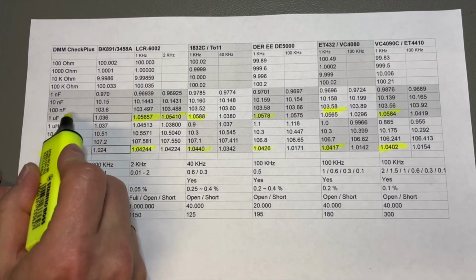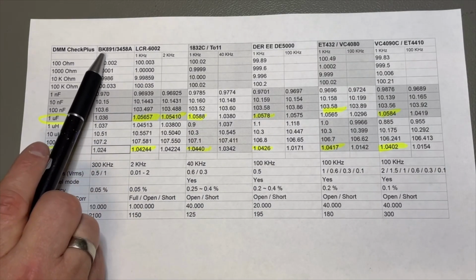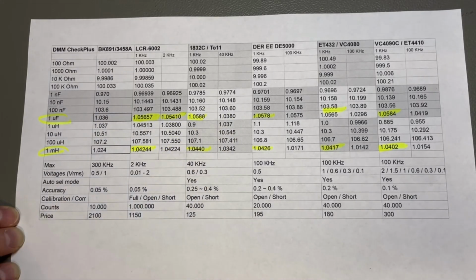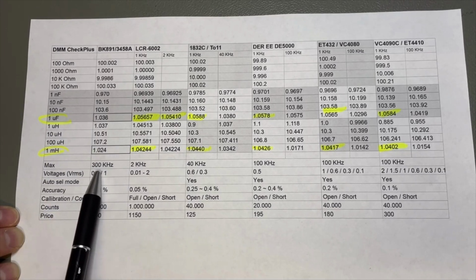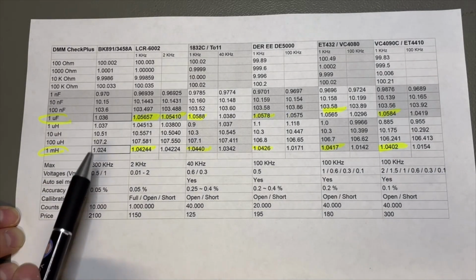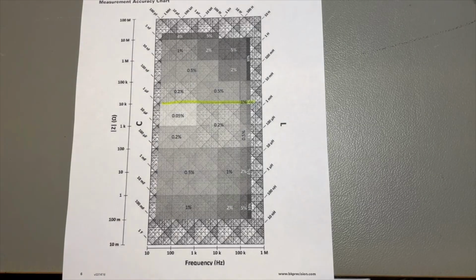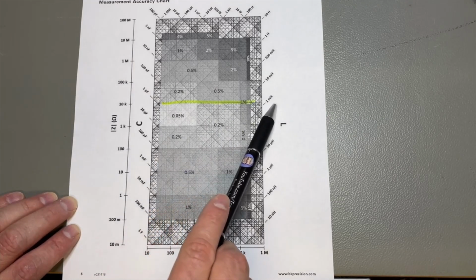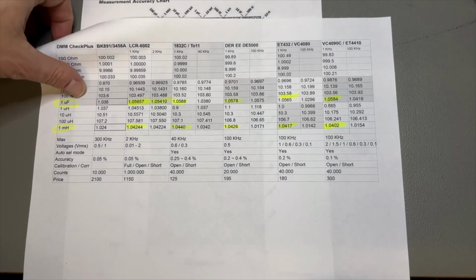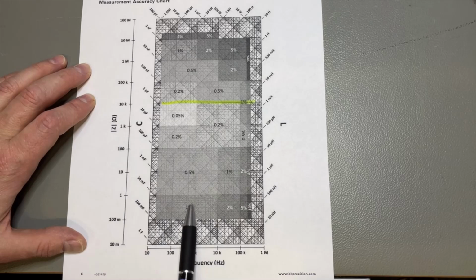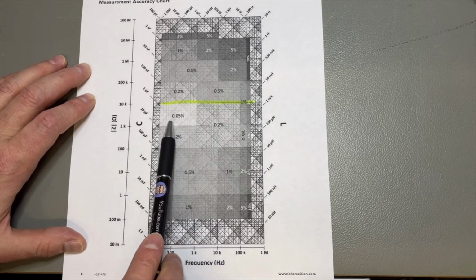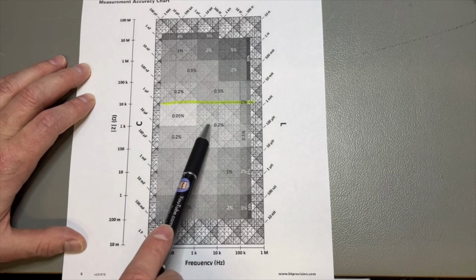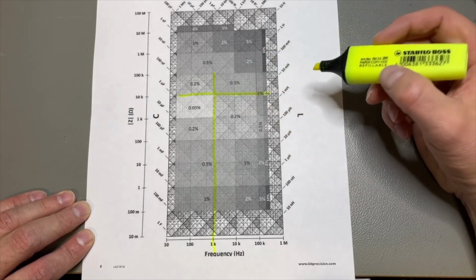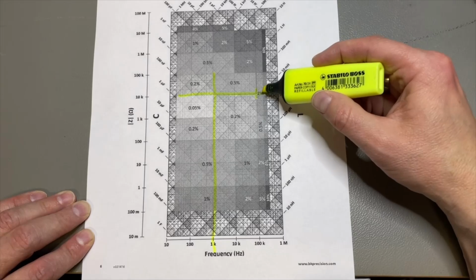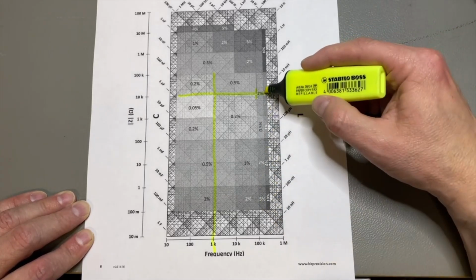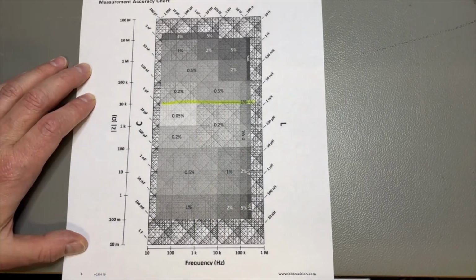So what happens with this calibrated value? Well, it is done with the BK891, and we saw that higher frequency gives more accuracy, but only up to a certain value, and this one goes up to 300k. I can't find in the documentation which frequency they use to measure these upper values. Then I found documentation of the BK891, and we are in the line of the 1 microfarad and the 1 millihenry, exactly what we measured here. Looking at the frequency, here we have the 1k line. If we go above 1k, the accuracy, which is 0.05 here, goes immediately to 0.2. So we can see what happens if we go above that. Even at 100k, we are already at 1%. So if they measured at 300k, we are probably somewhere around 2%. So that really means we need to stay around 1k.